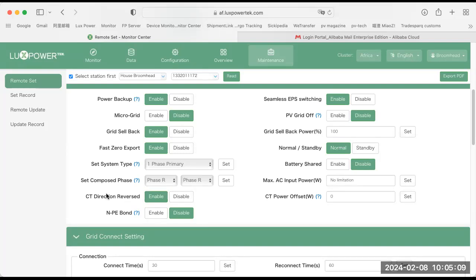Here we have a CT direction reverse function. You remember the CT clamp comes with an arrow on there, and it annotates the direction of the flow of current from the utility or from supply to the machine. But we know that sometimes the DB, or the wiring behind the cover of the DB, can look like a rat's nest, or it's very tight to get into. And once you fit the CT, it's maybe a little bit difficult to unclip it and turn it around.